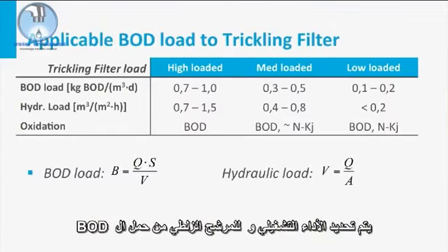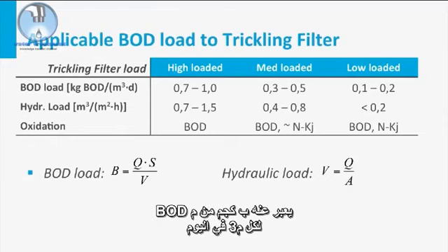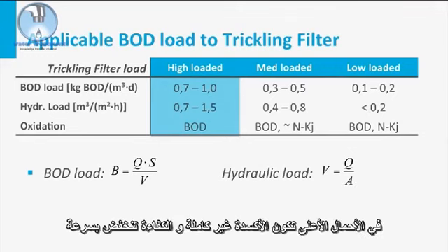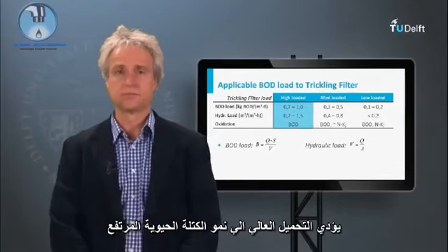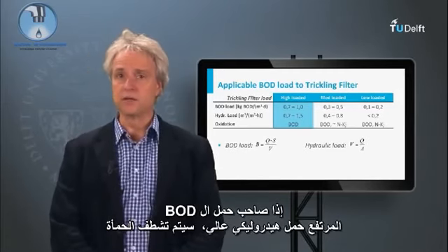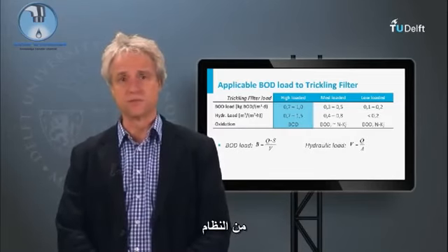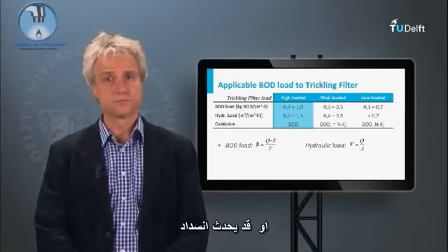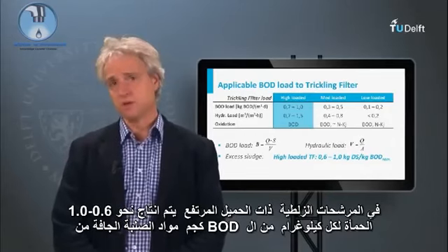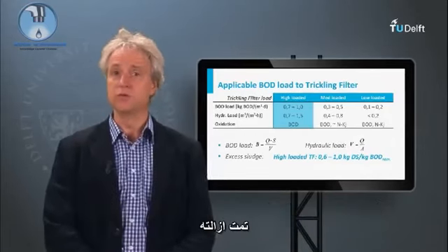Operation performance and functionality of a trickling filter is determined by the applied BOD loading, expressed as kg BOD per cubic meter volume per day. In a high-loaded system of 0.7 to 1 kg BOD per cubic meter per day, only organic BOD will be oxidized. At higher loadings, the oxidation is incomplete and the efficiency rapidly drops. The high loading causes high biomass growth. If the high BOD load is accompanied by a high hydraulic load, then the sludge will be rinsed from the system, otherwise clogging may appear. In a high-loaded trickling filter, about 0.6 to 1 kg dry solids of sludge per kg BOD removed will be produced.